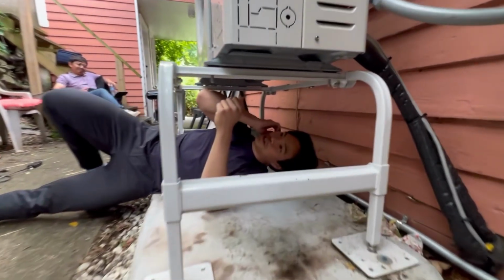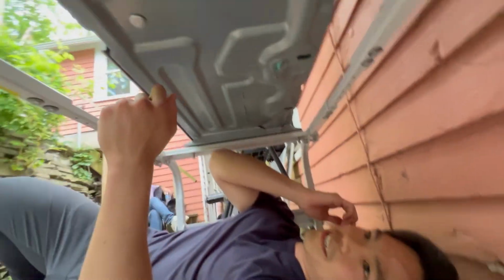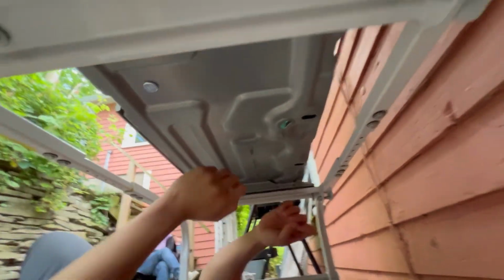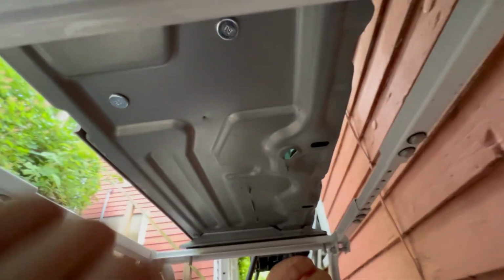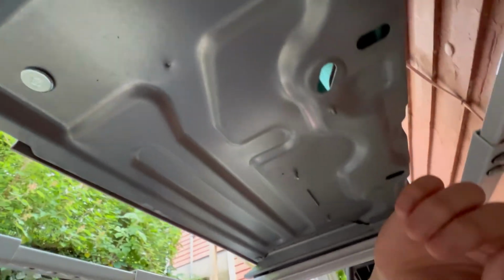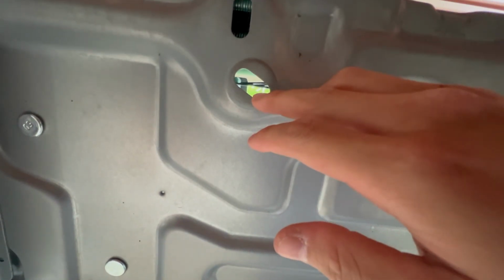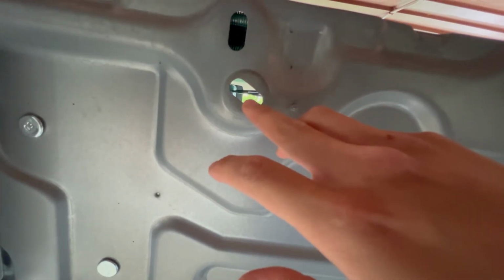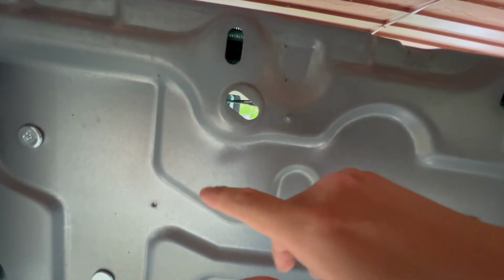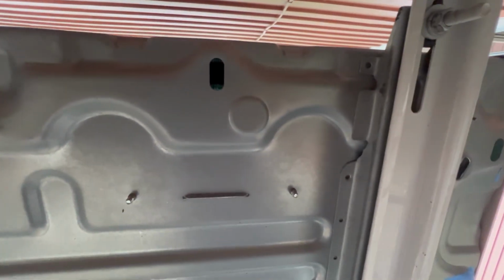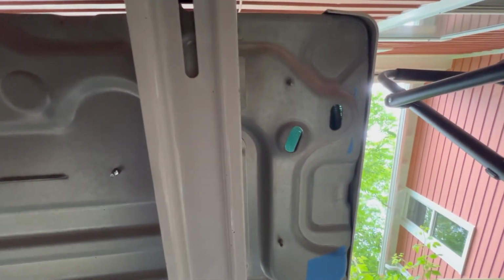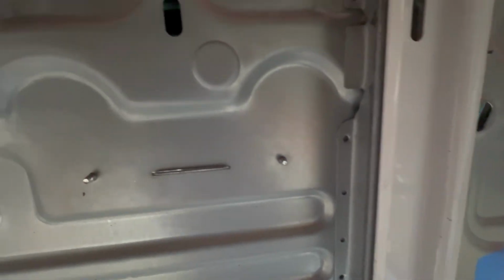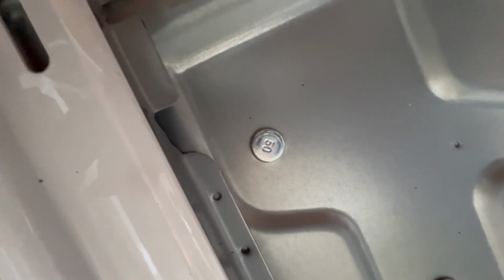Here, you now join me underneath the heat pump at the base pan. This is where we're going to see a lot of the condensate drain holes. And we did see them in action today when we were running the heat pump in cooling, where water would condense and drip out from these holes. These are also pretty good bypass sites, pretty significant bypass sites. And as you can see, there is quite a lot of them underneath this heat pump. And after sealing them, we reduced the CFM by around 30 CFM after sealing all of these holes.